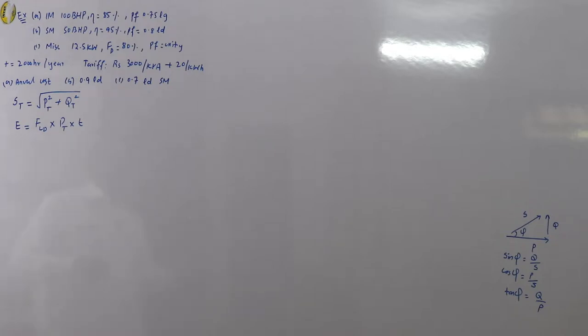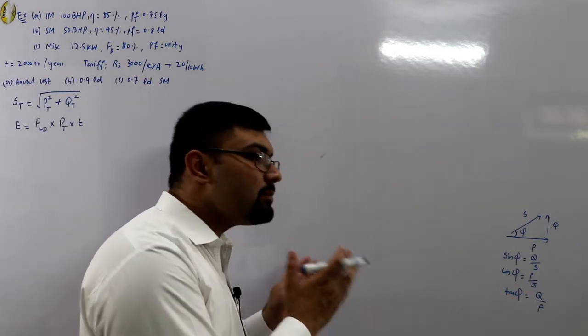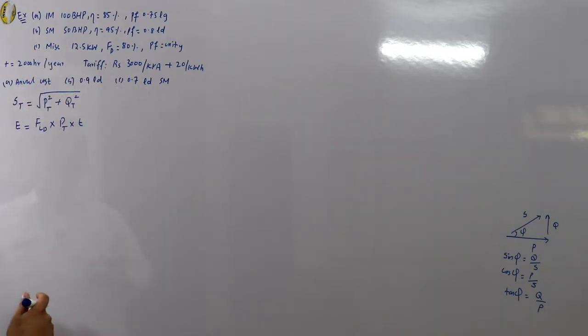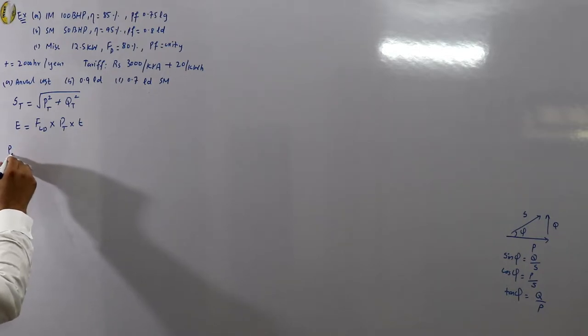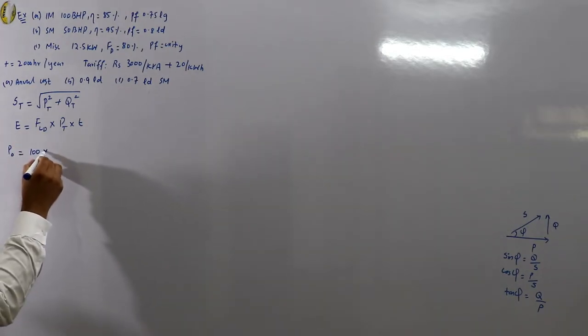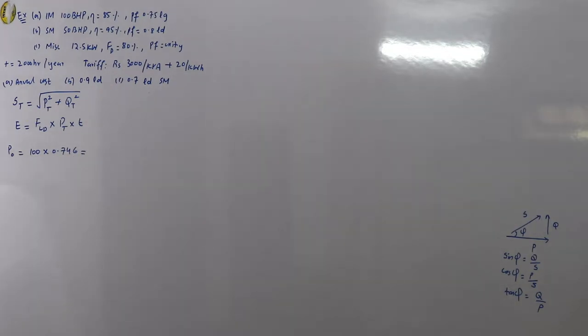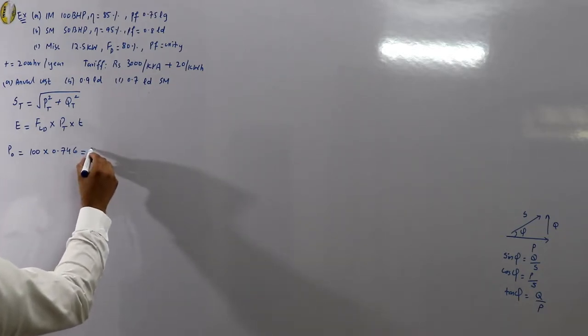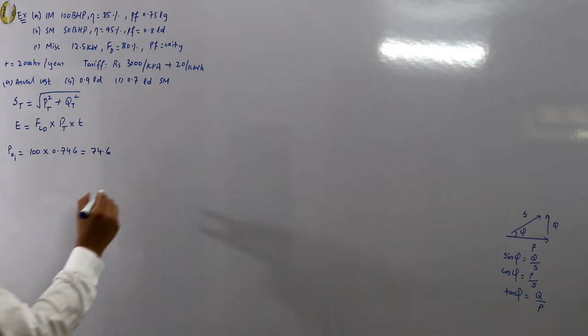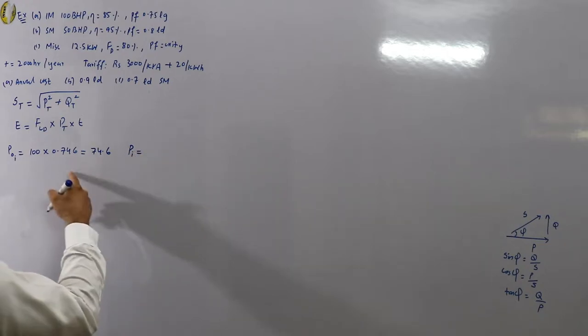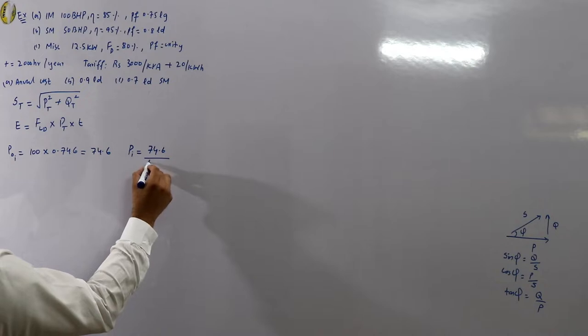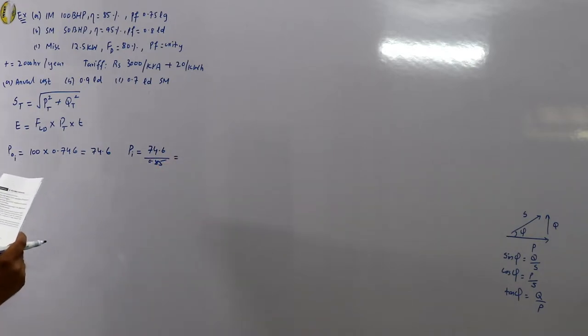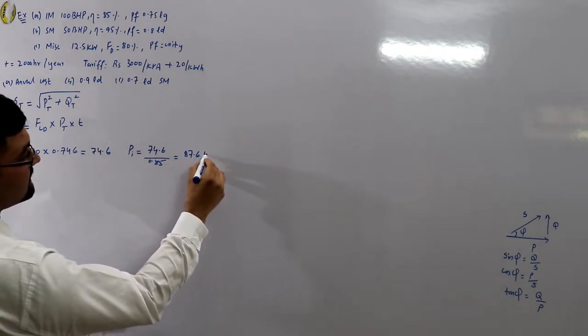The BHP values are the output of the motors, so we need the input. First, convert to kilowatts. For the induction motor, output power = 100 × 0.746 = 74.6 kW. Input power P_i = 74.6 / 0.85 = 87.6 kilowatts.